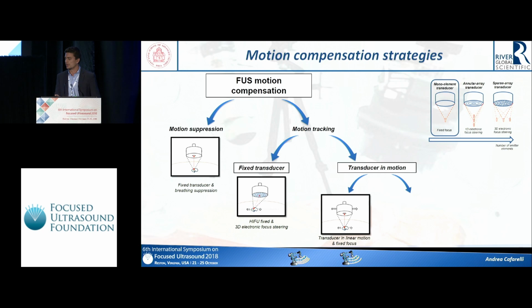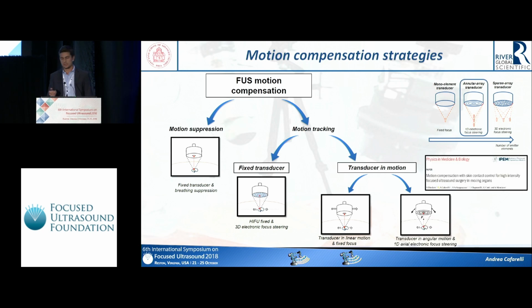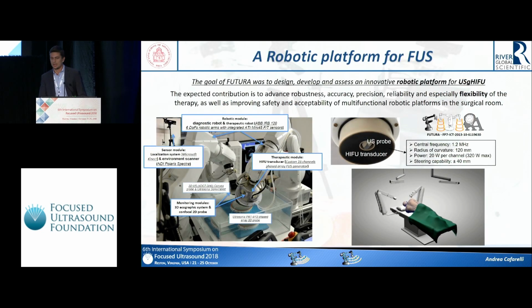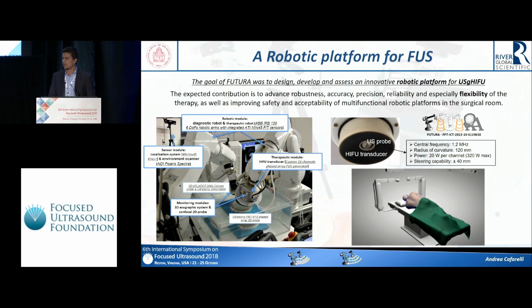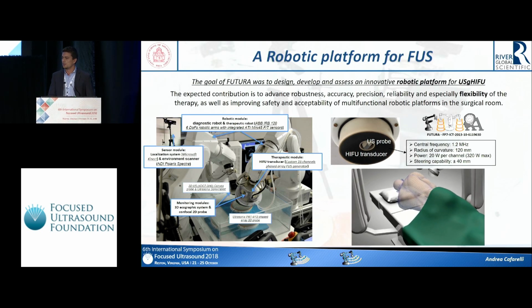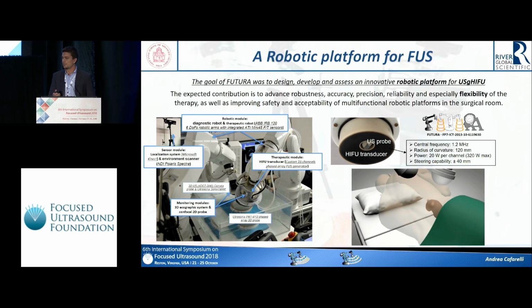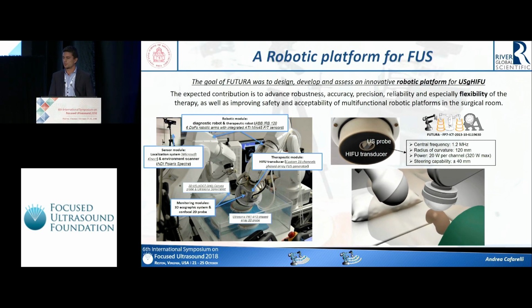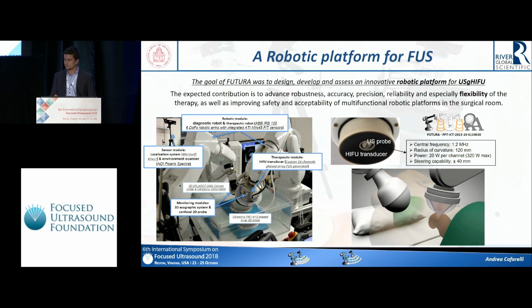We can move the transducer linearly, or the approach that we are proposing is to move the transducer angularly and then adjust the axial steering of the focus. This work comes from a European project, the Futura project, which aimed to develop a robotic ultrasound-guided platform for focused ultrasound surgery in abdominal organs. Briefly, the platform is composed mainly of 2 manipulators, one holding a 3D imaging probe, and the other one holding an HIFU transducer with a confocal 2D imaging probe.